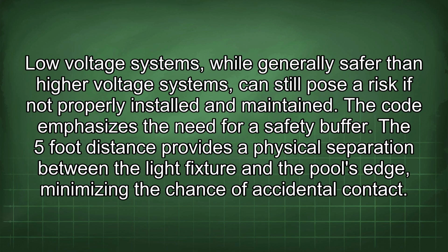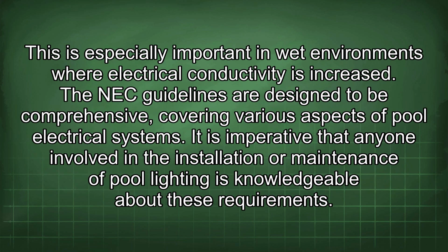Low voltage systems, while generally safer than higher voltage systems, can still pose a risk if not properly installed and maintained. The code emphasizes the need for a safety buffer. The 5-foot distance provides a physical separation between the light fixture and the pool's edge, minimizing the chance of accidental contact, which is especially important in wet environments where electrical conductivity is increased.